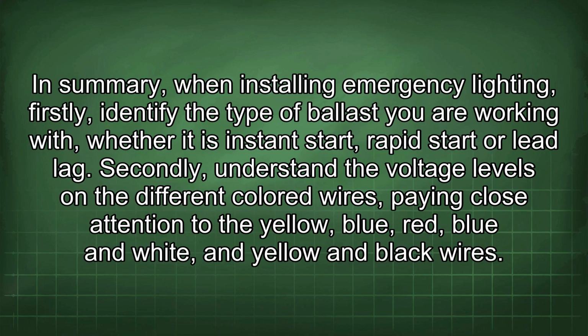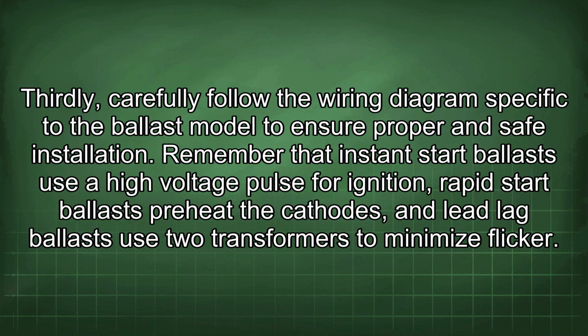In summary, when installing emergency lighting, firstly, identify the type of ballast you are working with, whether it is instant start, rapid start or lead lag. Secondly, understand the voltage levels on the different colored wires, paying close attention to the yellow, blue, red, blue and white, and yellow and black wires. Thirdly, carefully follow the wiring diagram specific to the ballast model to ensure proper and safe installation. Remember that instant start ballasts use a high voltage pulse for ignition, rapid start ballasts preheat the cathodes, and lead lag ballasts use two transformers to minimize flicker.